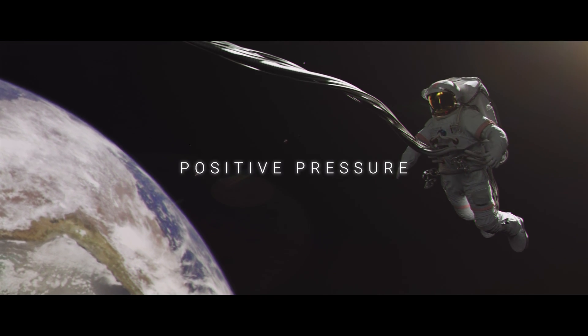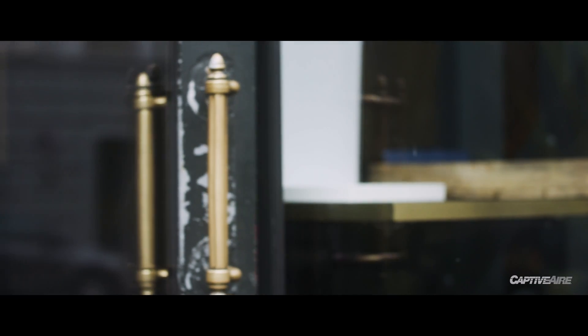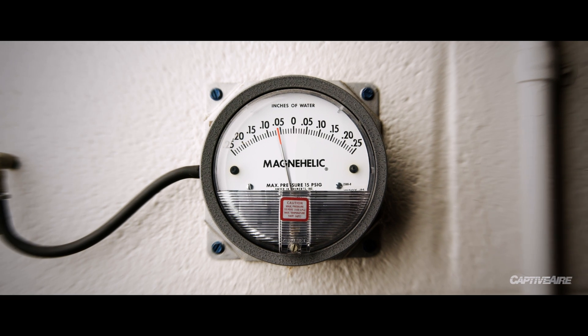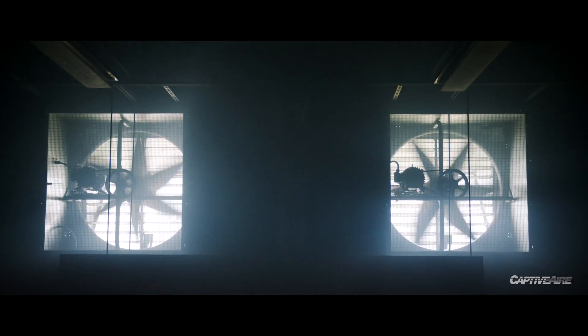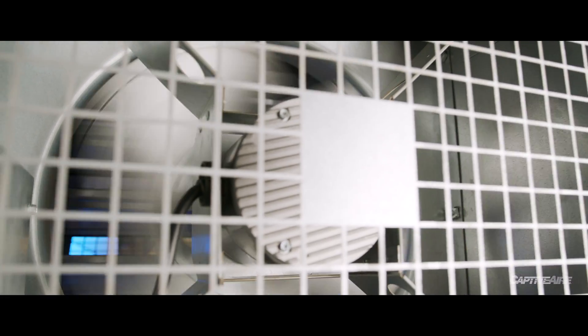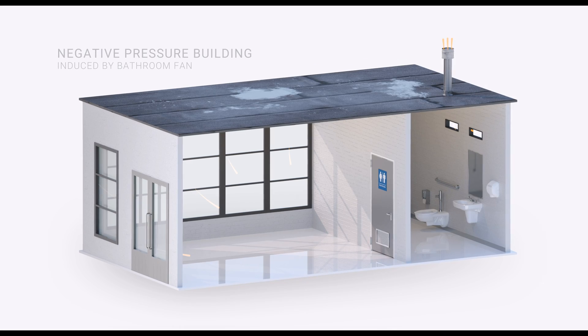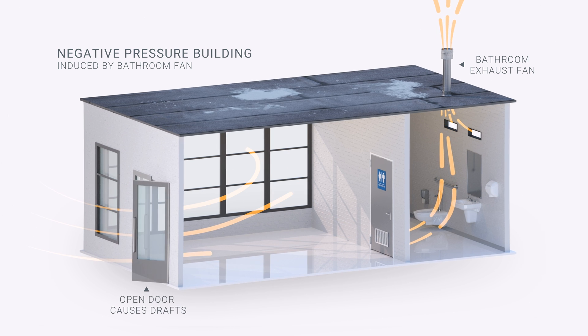If you've ever been sitting next to a door and someone opens it and cold air rushes inside, that's because the building is under negative pressure. Positive building pressurization is key to making comfort work. When you have an exhaust load in a building, that air has got to come from somewhere. If you don't have enough positive pressure, it comes from every little nook and cranny and crack and crevice in the building, and that air is untempered.